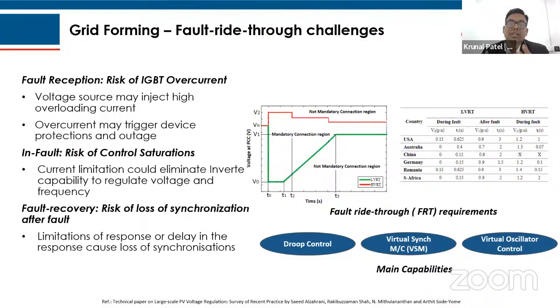If a single inverter is not in synchronization mode with all the other inverters, there may be a chance of circulating current flowing, and because of this circulating current, a loss of synchronization may happen. For that, multiple technologies or capabilities are generally developed in the grid forming inverter. One of them is a droop control mechanism. It should have virtual synchronous machine characteristics, and it should act as a virtual oscillator control. In this way, the grid forming inverter can handle the various fault ride through challenges which can be generated in a microgrid.